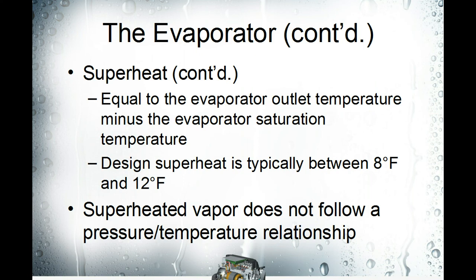We'll go through this in great detail, because this is what you need to do to charge and check the system. One of the measurements is superheat, and superheat is equal to the evaporator outlet temperature minus the evaporator saturation temperature. Most air conditioning systems will have the design superheat in the operation and maintenance manual, but a good rule of thumb is between 8 and 12 degrees Fahrenheit of superheat. One thing that trips up newer HVAC techs is they start looking at the pressure temperature chart, which is a saturated state of the refrigerant — superheated vapor does not follow the pressure-temperature relationship found on the pressure temperature chart.